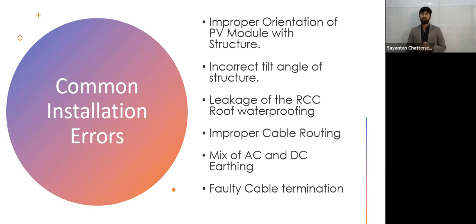And the most irritating mistake that we solar people sometimes make is mixing AC and DC earthing as well as lightning arresters. I have seen a few plants where the lightning arrester is connected in the same earth pit where the inverter is connected. So we are inviting lightning and giving it a path to damage our equipment. So in any solar plant, we have to ensure that the earthing is separated: AC earth pit, DC earth pit, and lightning arrester earth pit, with at least 1.5 or 2 meter spacing in between. And the earthing should be done as per IS 3043, just because it's a protection.